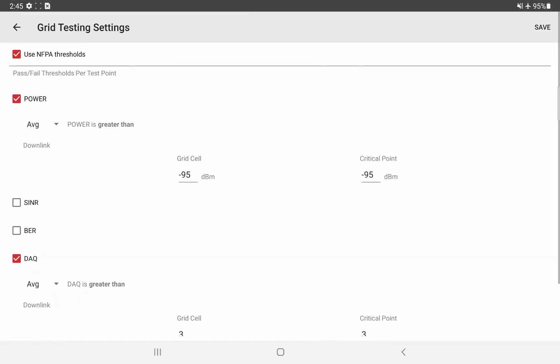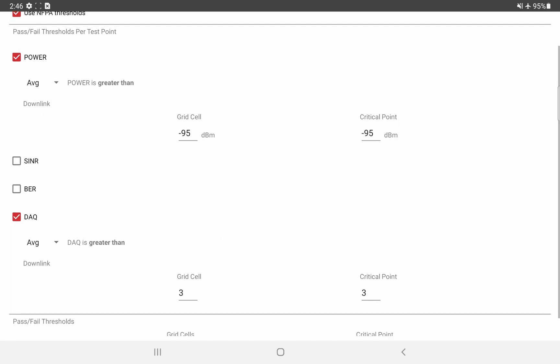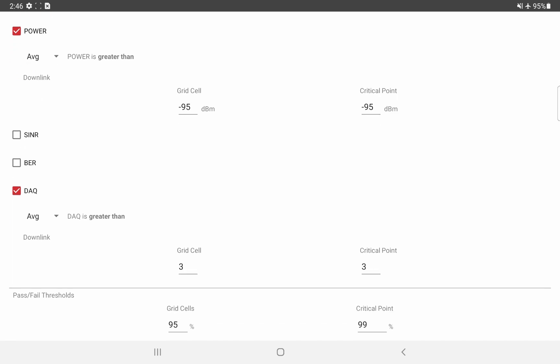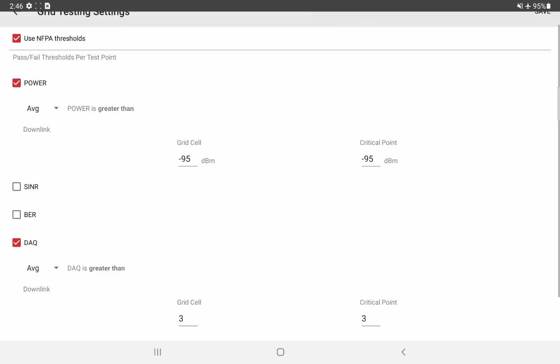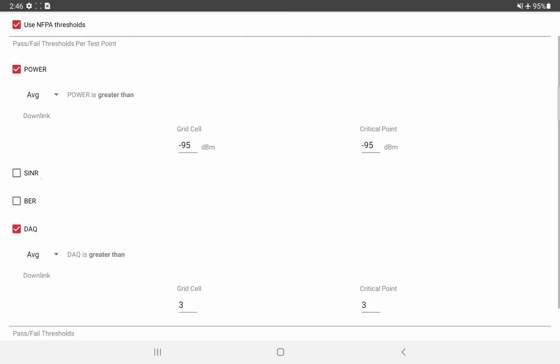Now, let's take a look at the settings. So these are our threshold settings. Again, we have the NFPA checkbox there that will populate it with the NFPA thresholds recommended from their documentation. They ask for a power of minus 95 dBm, a DAQ score of 3 or higher, and 95% of general areas should pass and 99% of critical areas.